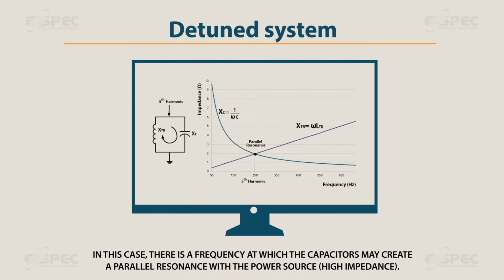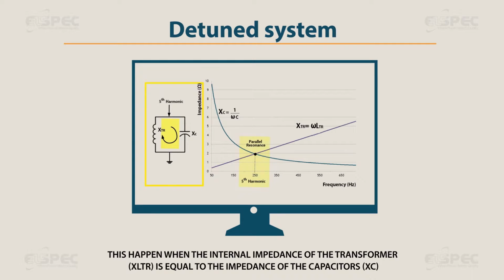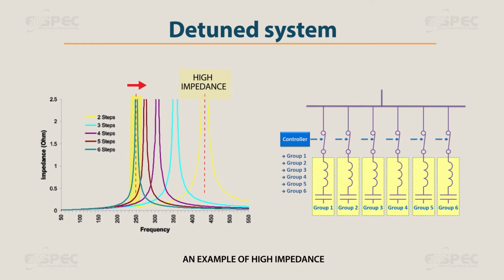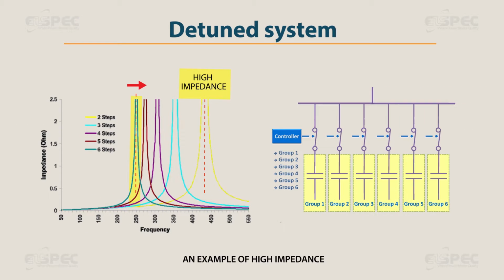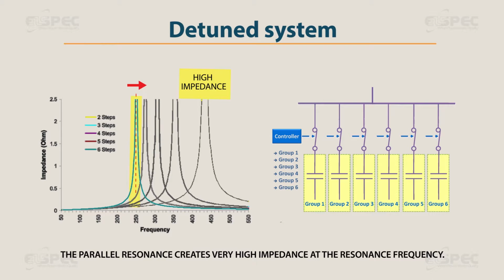In this case, there is a frequency at which the capacitors may create a parallel resonance with the power source, high impedance. This happens when the internal impedance of the transformer, XLTR, is equal to the impedance of the capacitors, XC. An example of high impedance. The parallel resonance creates very high impedance at the resonance frequency.